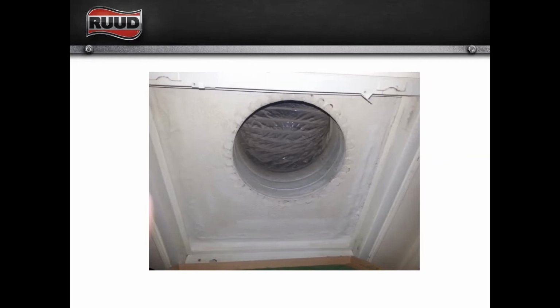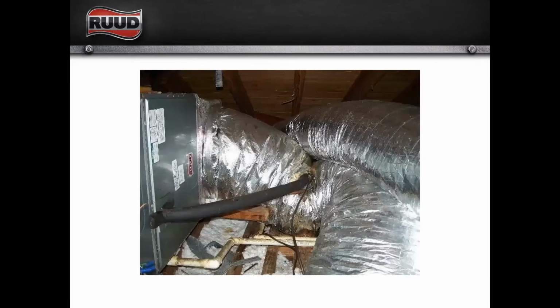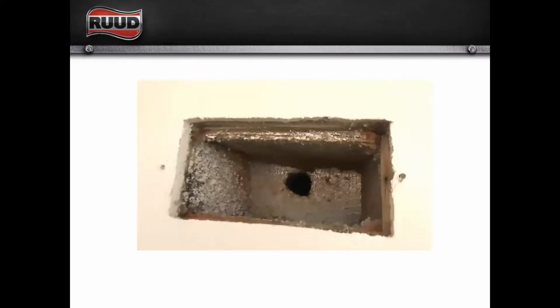And when we start talking about measuring static pressure, we'll go into exactly how you can find this. But this would be an example of when you're checking your static and you're looking at your return static and your supply static. If your return static's real high, you're not moving the air that you need to, and you've got to start investigating. But on the flip side, you might find a supply run where your supply static is higher than you would like to see it. And again, you might have to really start looking around and investigating.